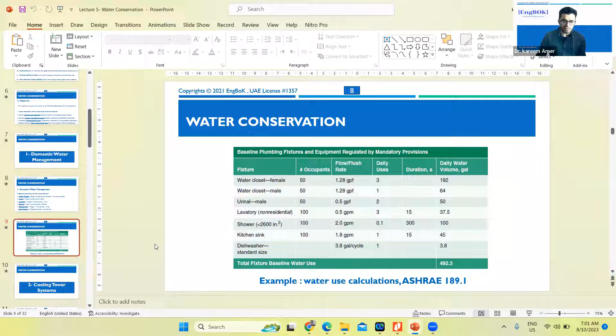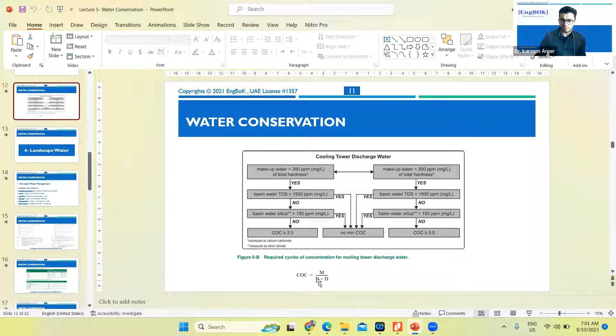We also cover cooling tower systems: the cycle of concentration in terms of make-up water required for the cooling tower, the drift from the cooling tower, and the blow down. This is also very important because it always comes up in the exam. This is the key equation for cycle of concentration: make-up water divided by blow down and drift. This is the water balance diagram.